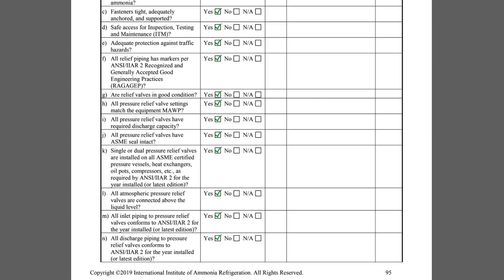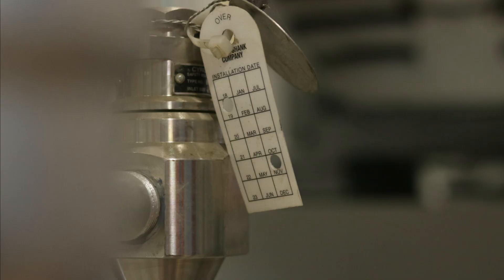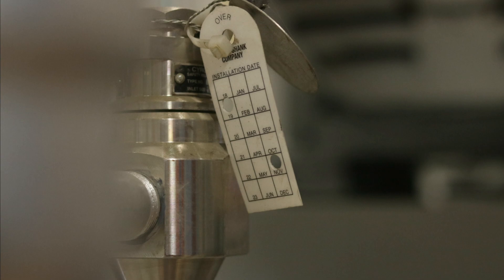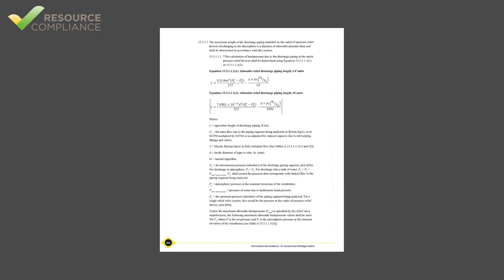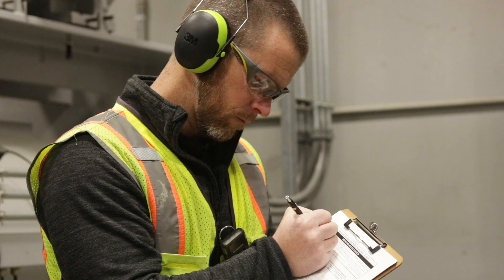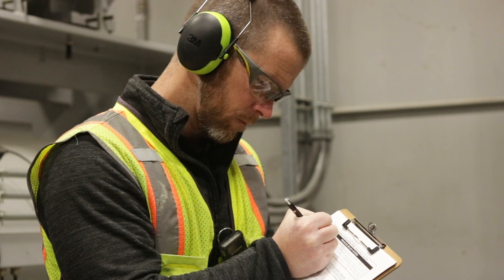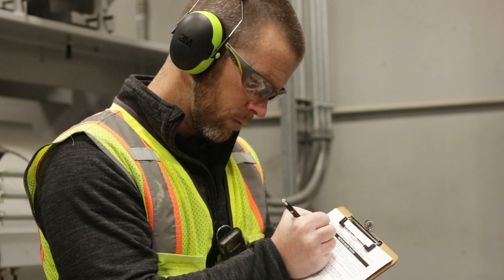Similarly, Item N inquires if the relief valve discharge termination piping conforms to the edition of IIAR Standard 2 applicable when the relief system was installed. The equation for assessing discharge piping for excessive back pressure can be a bit intimidating, but at minimum, the inspector must verify that there are no reducers in the termination piping.